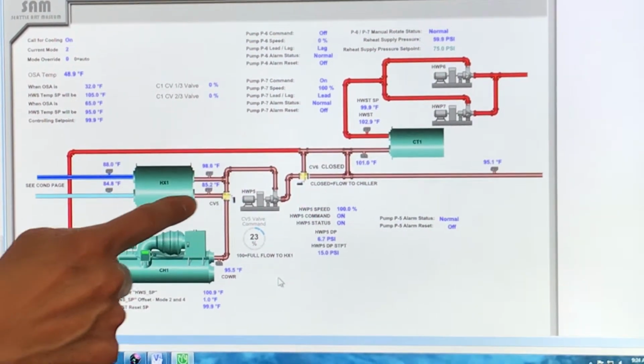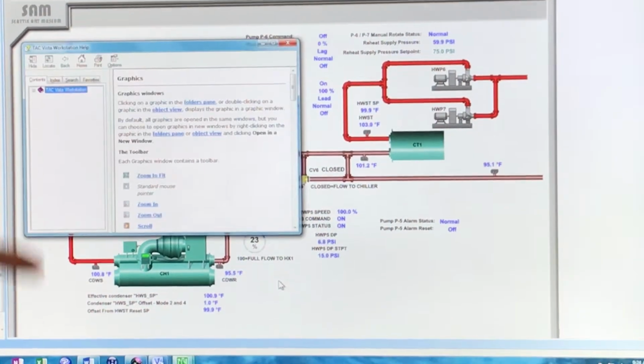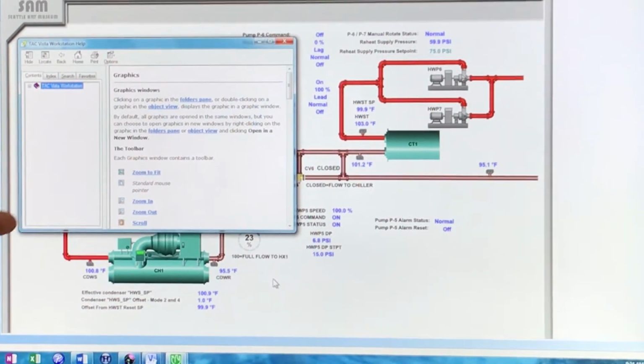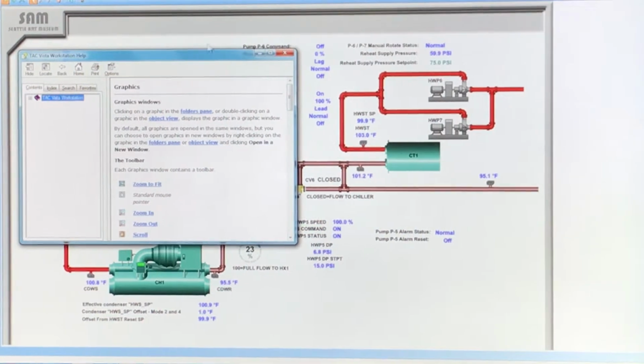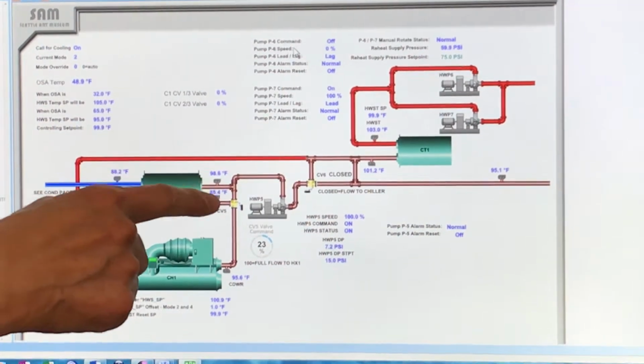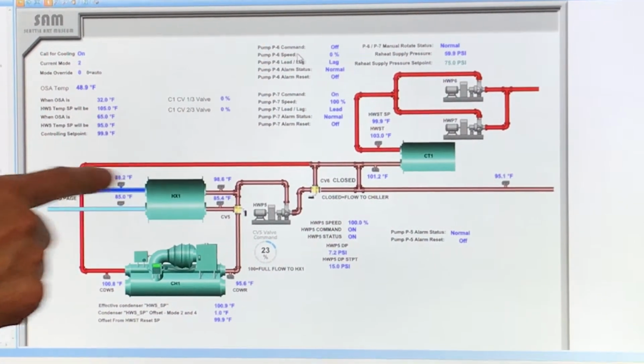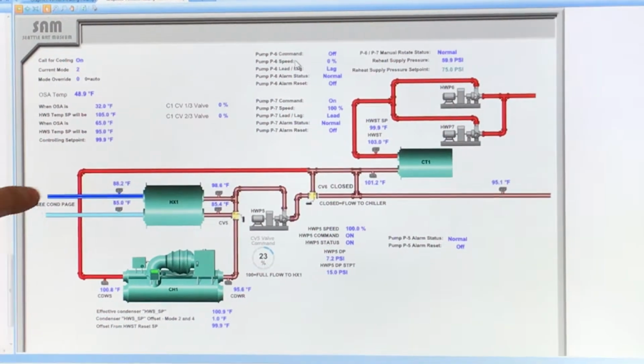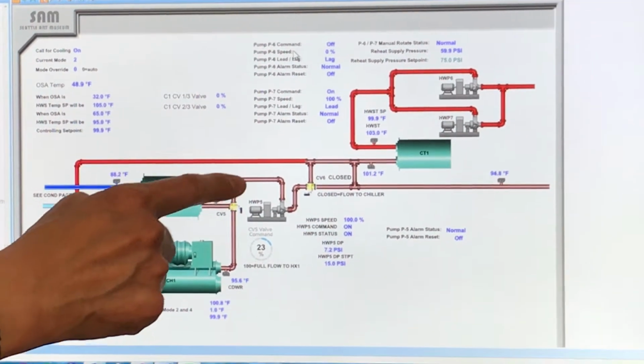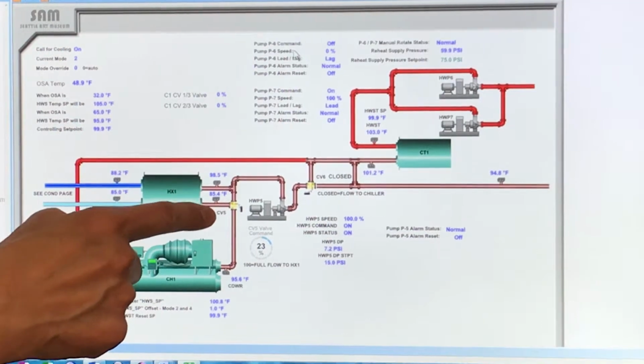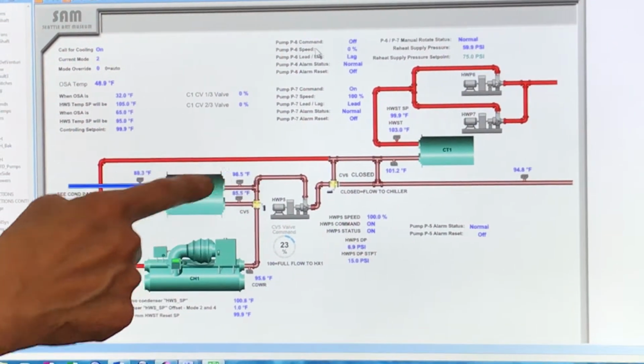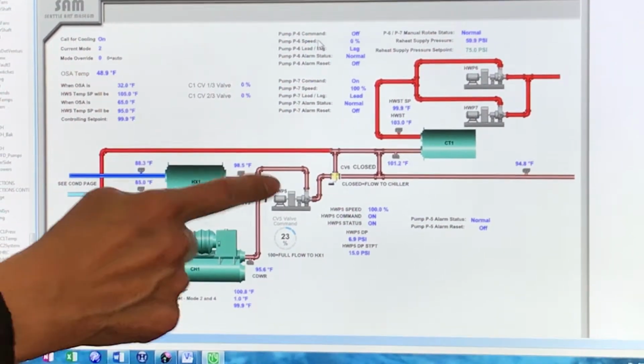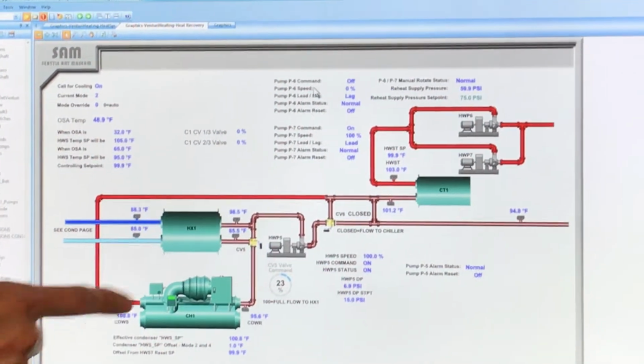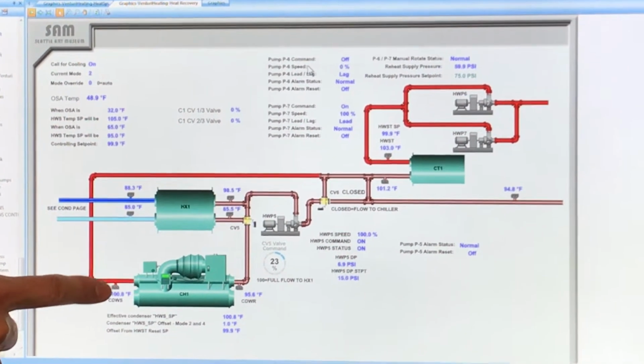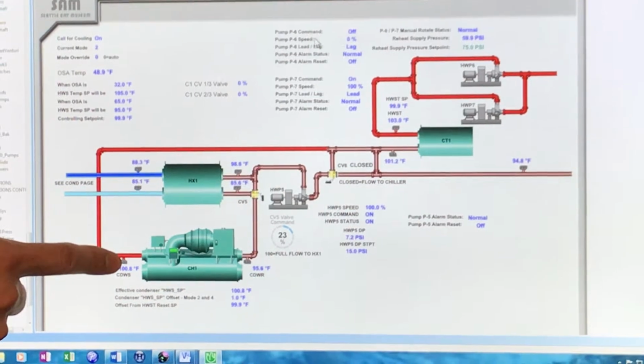So when you are going through here, because the tower is always running, and sorry. How you did that? I don't know. I mean, I must have touched the keyboard. So Oh. the tower is running, and so you have the cold media here, and then when you go through here, the temperature will drop when you pass through the heat exchanger, and this valve modulate based on that set point.